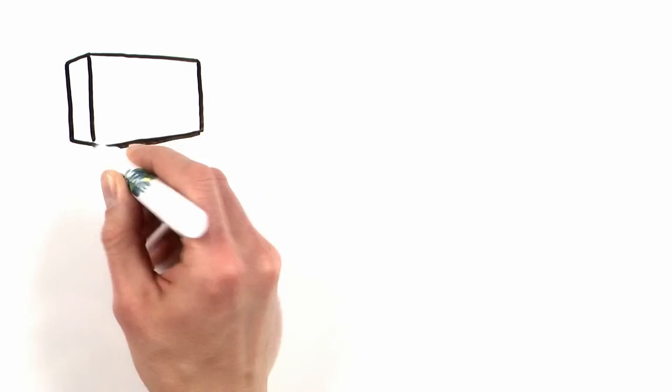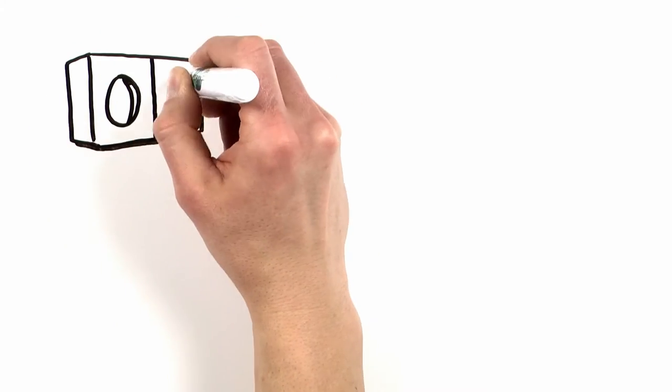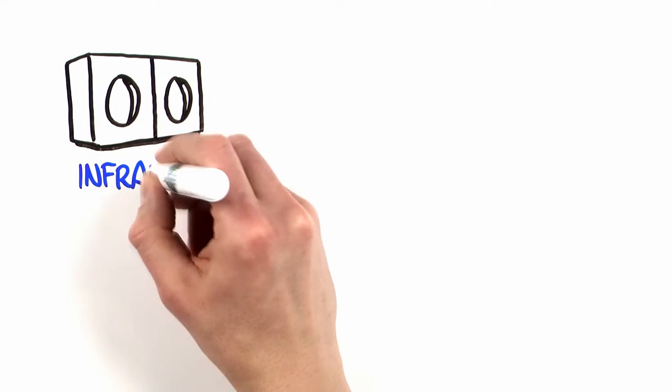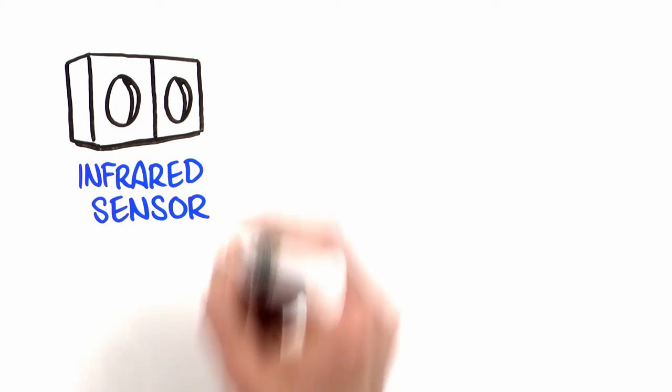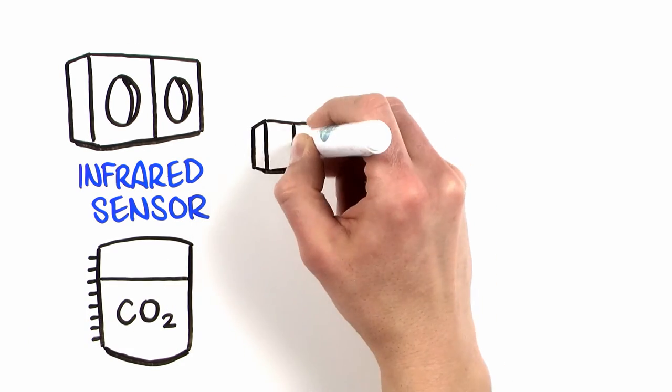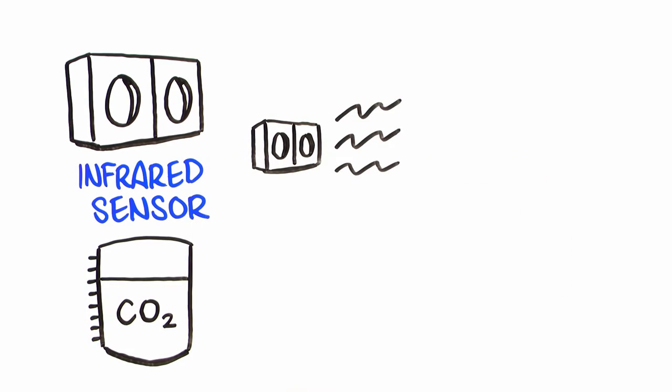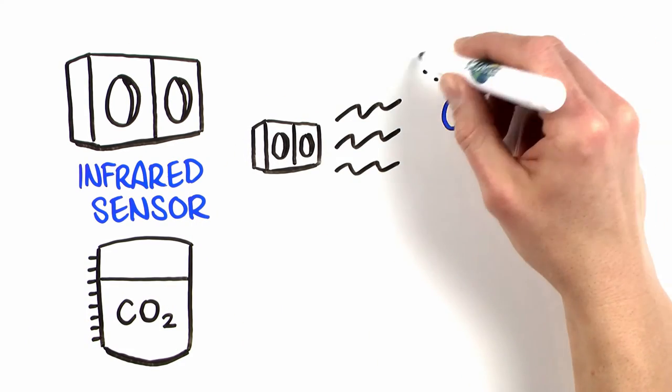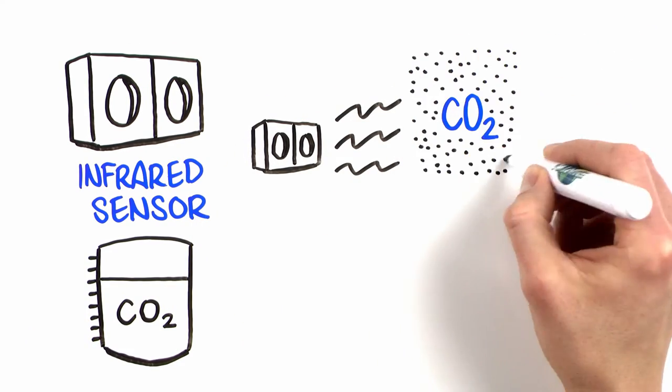Then it uses a microprocessor-based, non-dispersive infrared sensor to measure CO2 volume. Specific IR wavelengths are absorbed only by CO2, making measurement insensitive to other gases and water vapor.